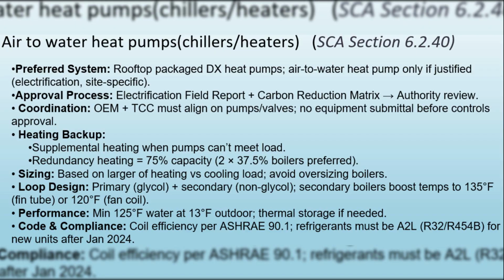secondary loop. Secondary loop boilers raise hot water to about 135 degrees Fahrenheit at 13 degrees Fahrenheit outdoor conditions for fin tube radiation, or about 120 degrees Fahrenheit for fan coil units. Air handlers and vertical unit ventilators in the primary loop still need their own resistance heating for backup since the secondary boilers don't cover them. Manufacturers can provide at least 125 degrees Fahrenheit water at 13 degrees Fahrenheit outdoor temperature, and that is the design baseline. If needed, a thermal storage tank may be added to maintain minimum water volume. Coil selection must also follow ASHRAE 90.1 efficiency rules, with certain exceptions for high-pressure drop or special systems. Finally, all units must comply with all listing standards.